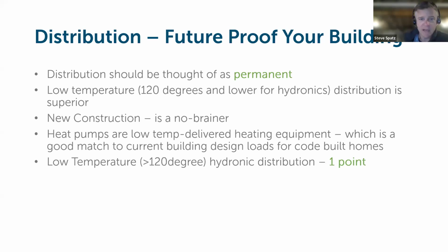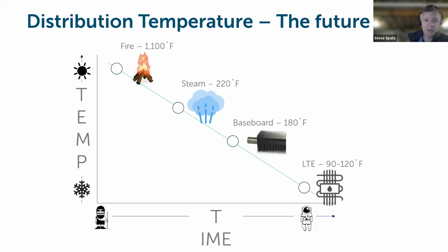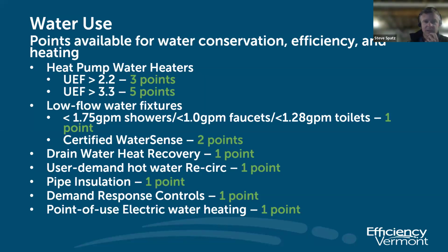If you're using a condensing gas, propane, or natural gas boiler, the lower the water temperature delivery moving into the house and the higher the delta is between the energy going into the house and what's coming back into the furnace or boiler, the more efficient that furnace or boiler is going to run. So it's the same methodology, no matter which one we're talking about, heat pumps or fossil fuel equipment. So really consider the distribution system as a fixed asset for the building, no matter what heating system you put in at the time the house is built. At some point down the road, 20, 30 years, hopefully at least that long, that piece of equipment is going to need to be replaced. But you're not going to be replacing your distribution system at that time as well. So, just future proofing and consideration in the overall system design.